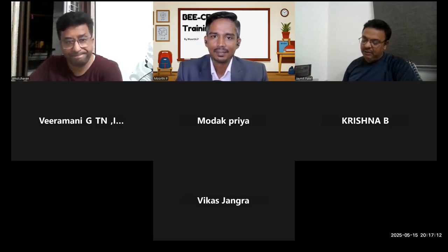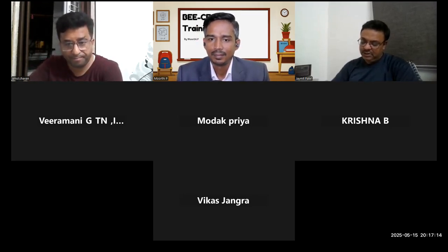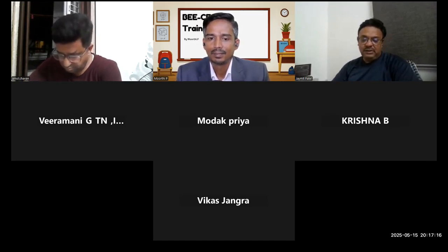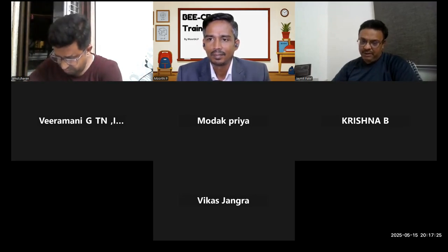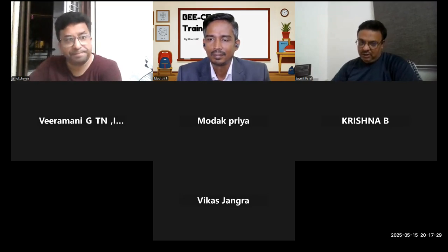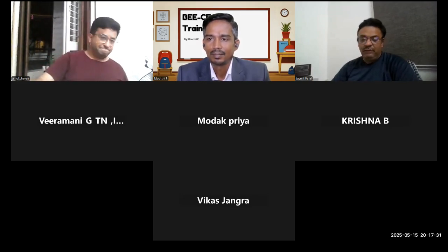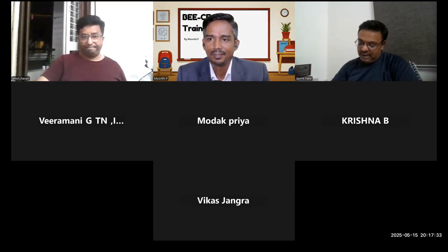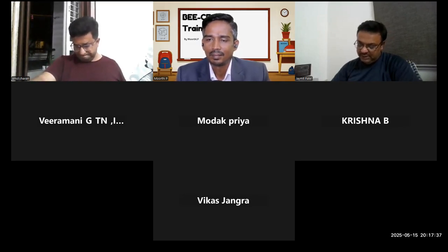After that, find the actual mass of dry flue gas. The mass of dry flue gas is equal to mass of CO2 in flue gas plus N2 in fuel plus N2 in combustion air plus O2 in flue gas plus SO2 in flue gas. And then we found the mass of the dry flue gas. Step 5 is to find all the losses.